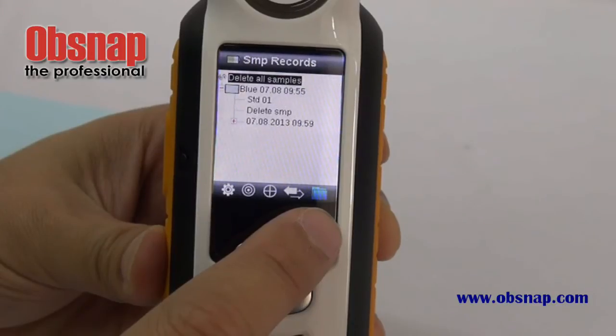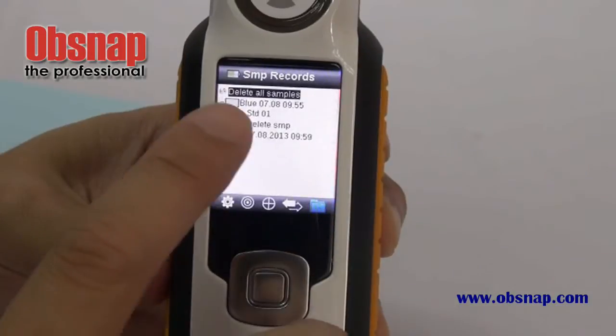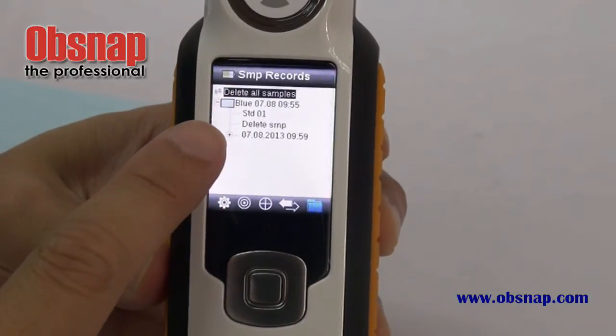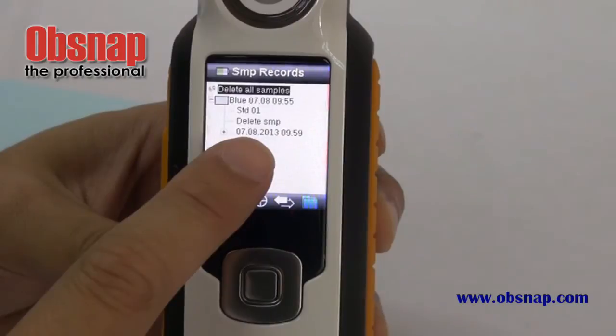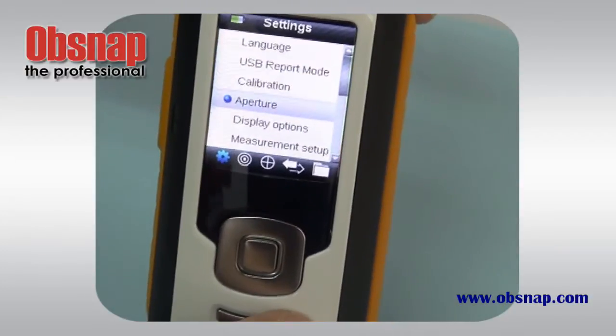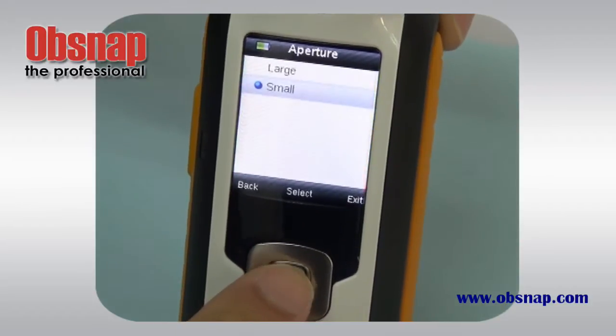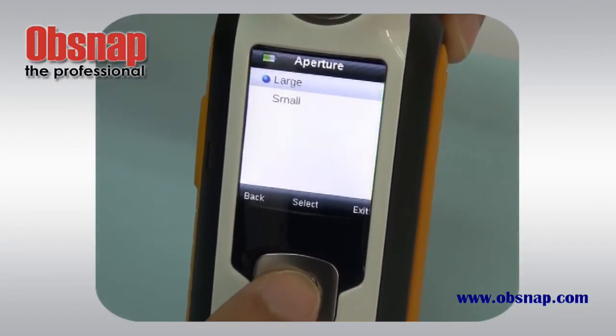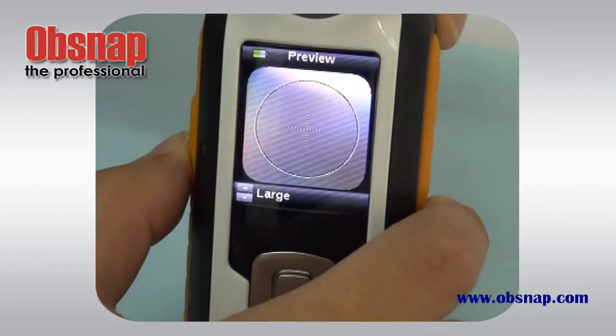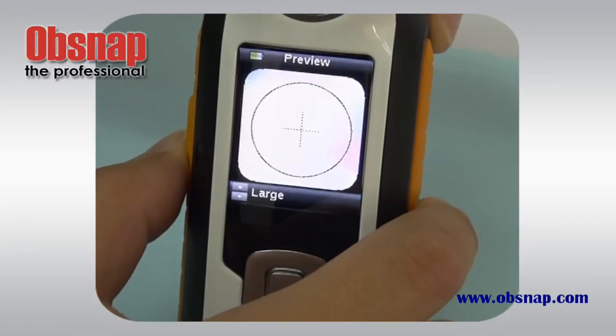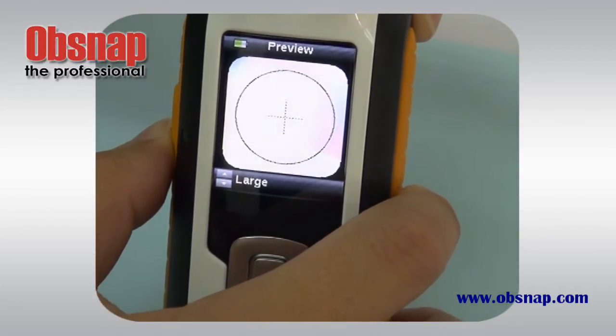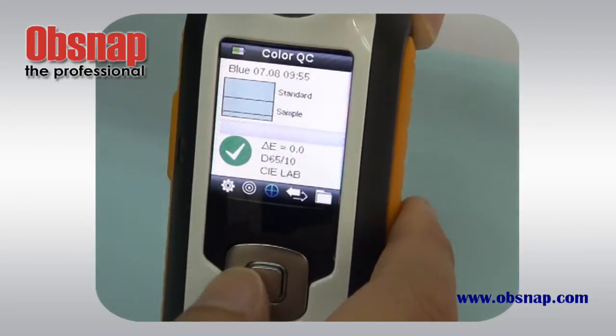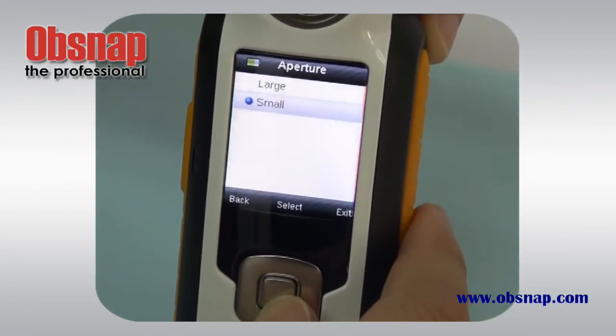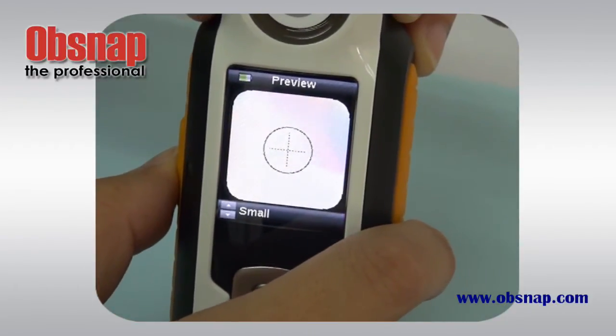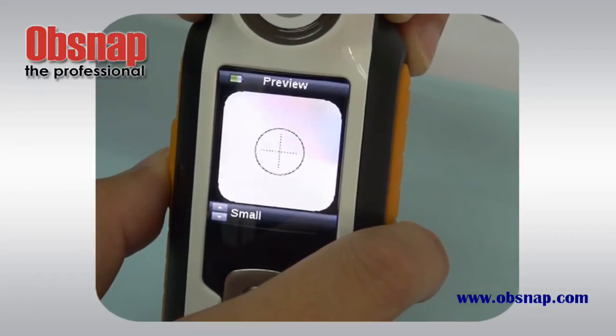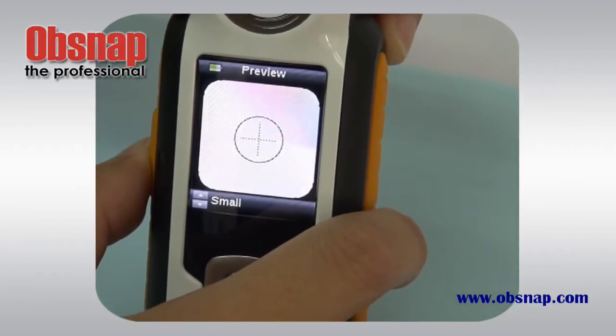And the last menu selection is actually to show us the sample record. We can delete all the samples from here and we can view the sample measurement date and time from these selections. This RM200QC is able to switch the aperture from large to small. When we select large, this will be the large aperture size, and we can measure everything inside the circle, which is the area that we are going to measure. And we can select small aperture, and the circle will become smaller. This is actually good for us to measure on a very small part.